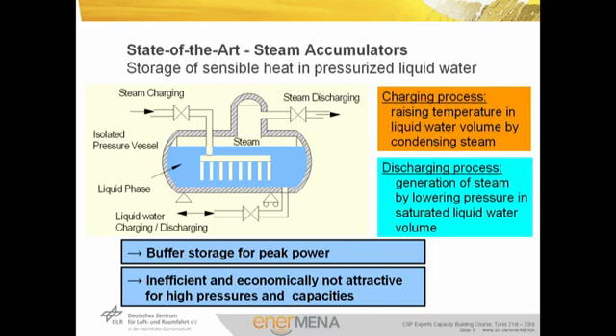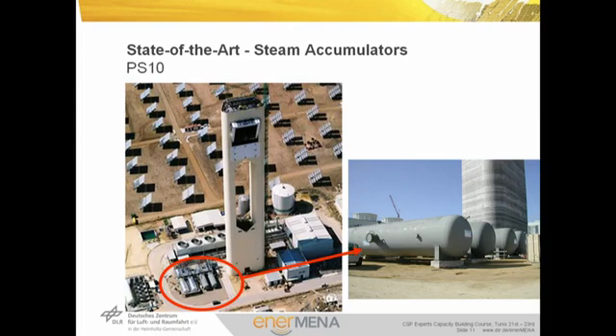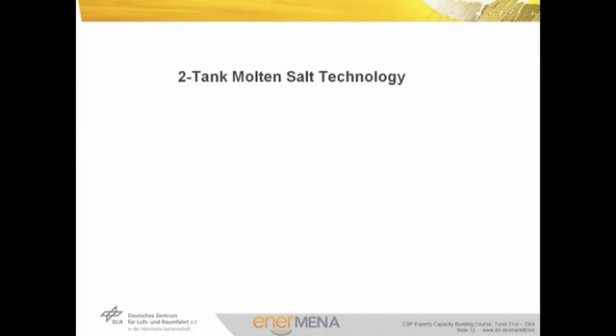Steam accumulators are preferred as buffer storage used for providing power for a short period. The capacity-specific costs are dominated by the expense for the pressure vessels and increase significantly at higher temperatures. An exemplary application for steam accumulators are the PS10 and PS20 power plants, which use saturated steam as working fluid produced in a central receiver. Steam accumulators are used to operate the power blocks during a period of about 50 minutes at 50% power. Main components of these storage systems are four pressure tanks filled with liquid water. Steam accumulators were chosen for the PS10 plant since this was the only commercially available storage concept at the beginning of construction.